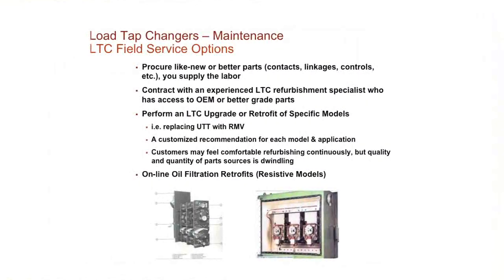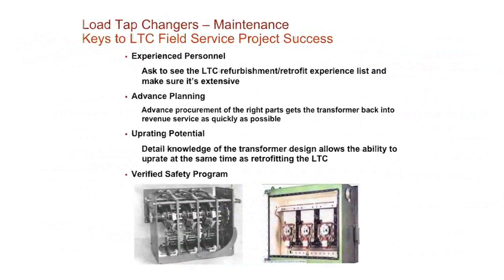But the main thing is to look at the contacts and you can see the contact wear. And there's dimensions you need to be checking on those for tolerance levels to know whether you need to replace them or if they're acceptable to go on. You want to check the resistance in an LTC, the ones that are what we call reactance type tap changers. Basically, you're just verifying the resistance values, which is inside typically on these type transformers.